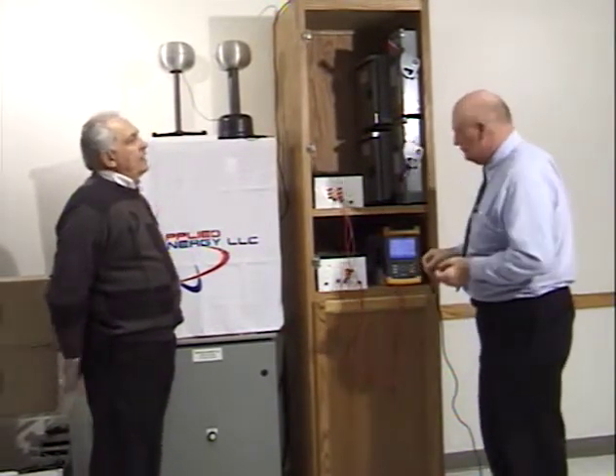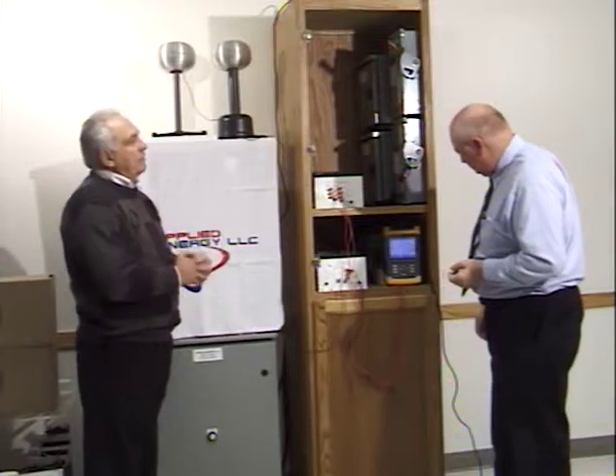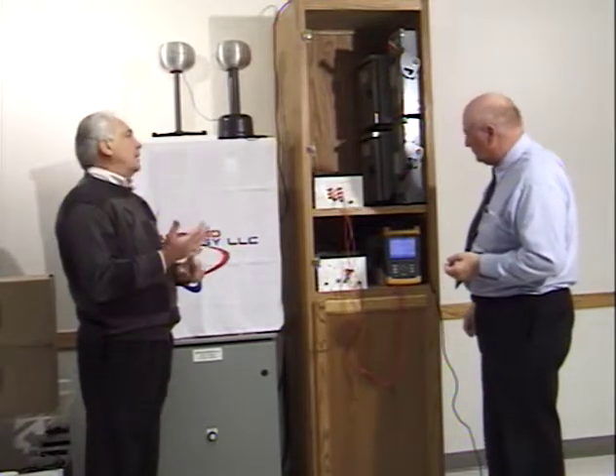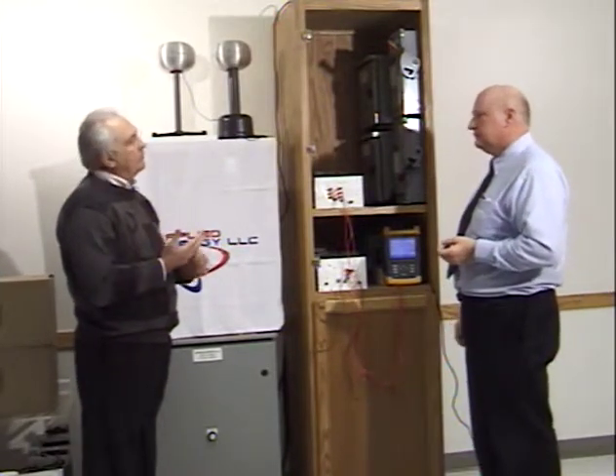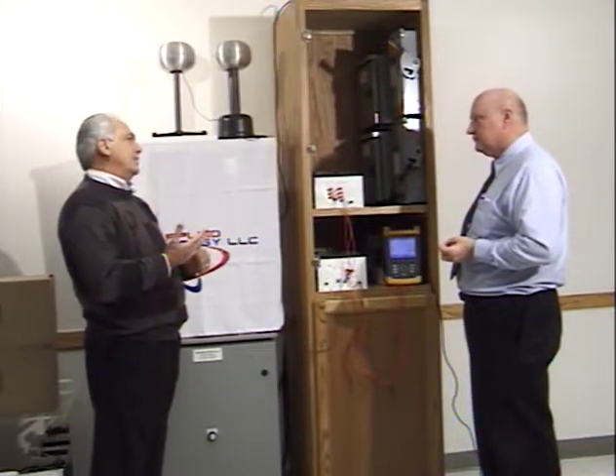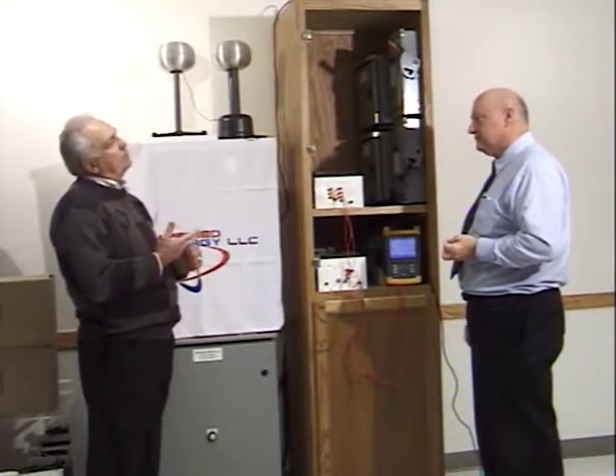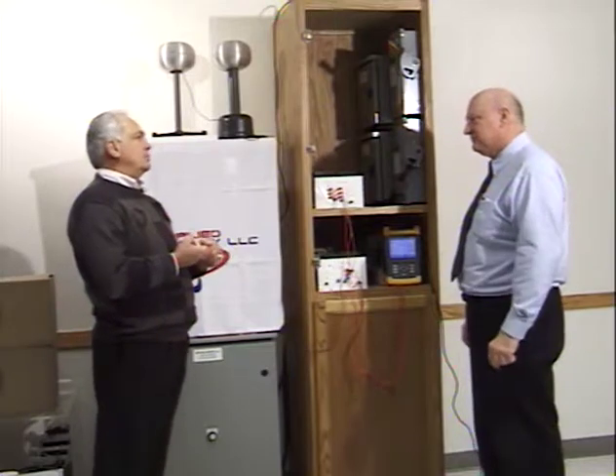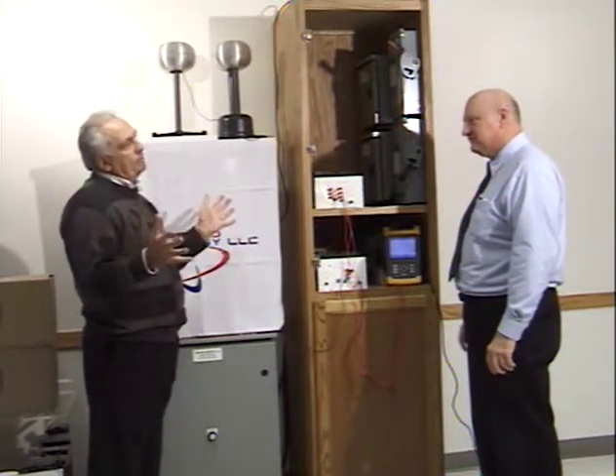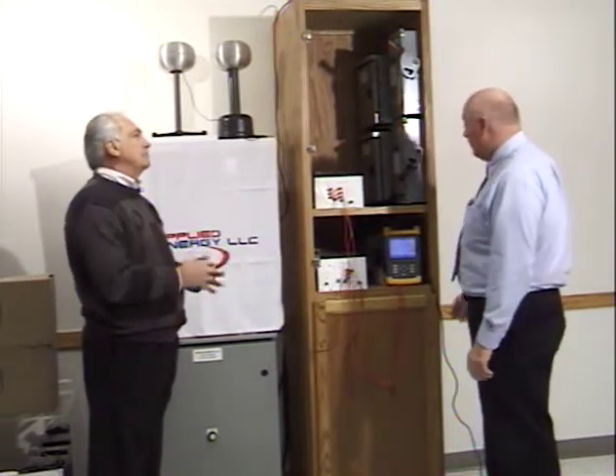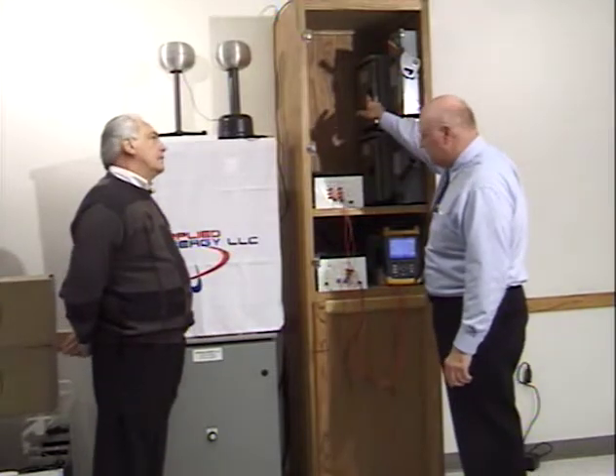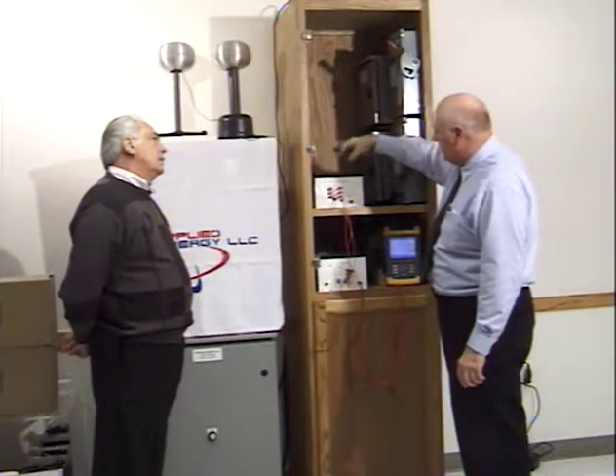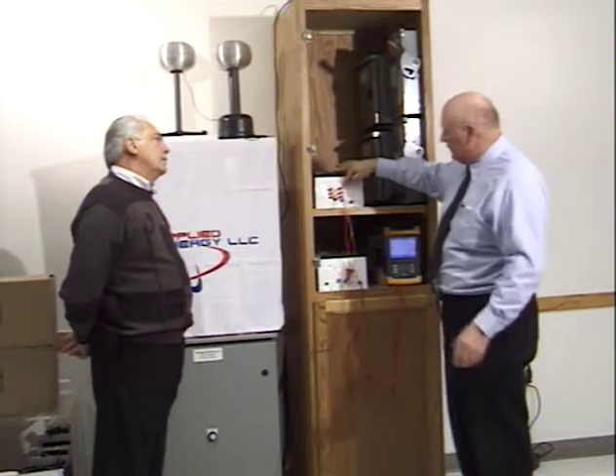So I guess in recapping, using the drive voltage stabilizer, we're stabilizing the waveforms as far as the voltage is, we're eliminating the transients that occur between the drive and motor, we're reducing the harmonics between the drive and motor. Quite a bit of benefit for one product. Right, and again, this is simply a smaller version of Phaseback in a new, unique application.